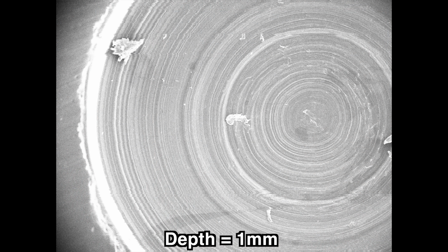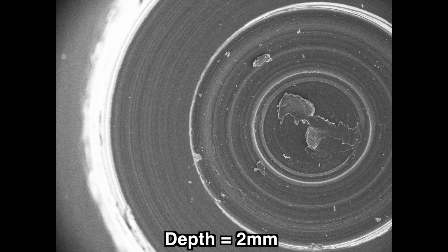Here is the hole that's 1 millimeter deep. You can see that the average brightness is about the same inside the hole as it is at the top surface. This indicates that the hole is not deep enough to meaningfully block the secondary electrons. However, as we increase the depth to 2 millimeters, you can see that the surface at the bottom is noticeably darker, indicating that fewer of the secondary electrons are reaching the detector.